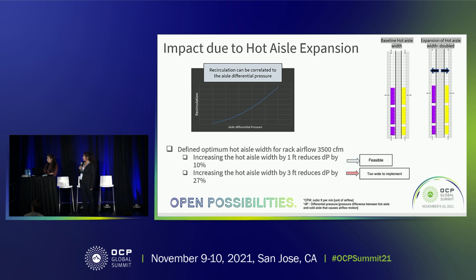We have run some CFD modeling to quantify what the impact would be if we include these design changes, say hot aisle expansion. We again did a similar analysis where we focused on 2 rows that would share a hot aisle. We increased the width of the hot aisle. Here, we are correlating recirculation to a parameter called aisle differential pressure. What I mean by that is it's basically the differential pressure between hot aisle and cold aisle measured across the side gaps of the racks. So when we increased the hot aisle width by 1 foot, we saw an aisle differential pressure reduction of 10%. And when we increased by 3 feet, we saw a reduction of 27%, basically showing an improvement in the secondary effect of recirculation.